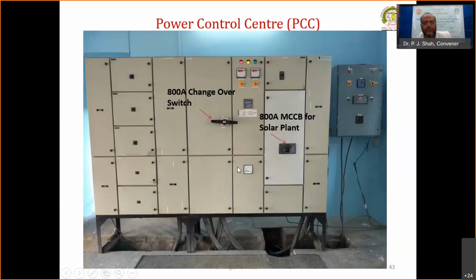Now in addition to this, this is our main panel. This is connected to one changeover switch, meaning MSEDCL grid power from the transformer and power from the DG set, whereas this part is isolated from the DG set. In any case, the DG power does not come into this section, and an 800 MCCB is connected especially for the solar. Now in this case, this is the ammeter which will indicate the solar current. This will show the grid current, because it is used in the other slides.